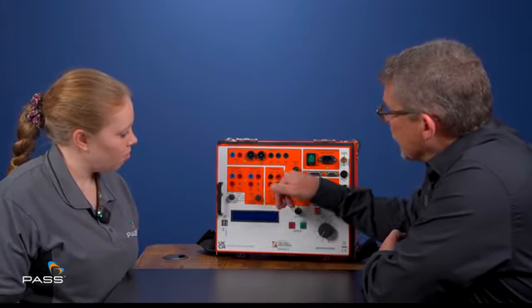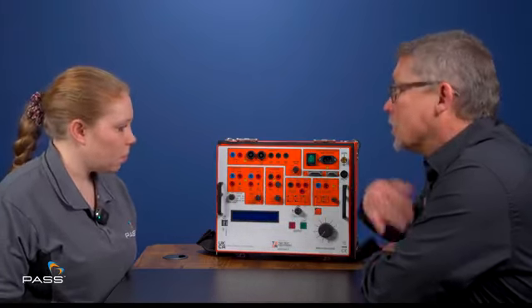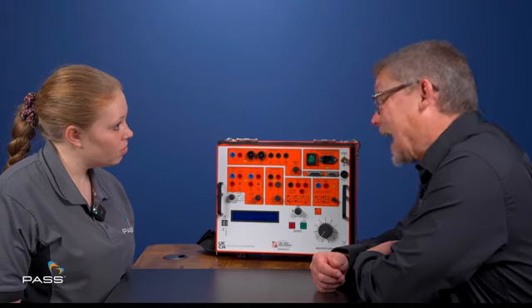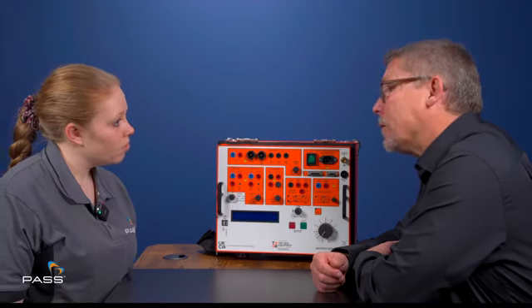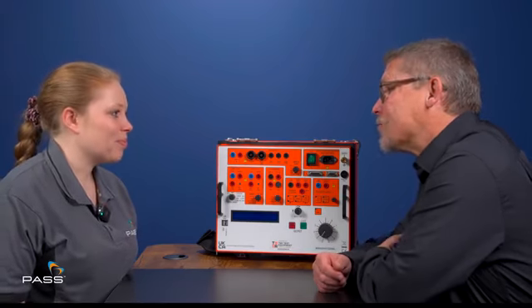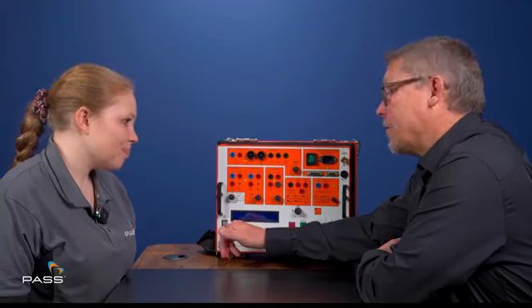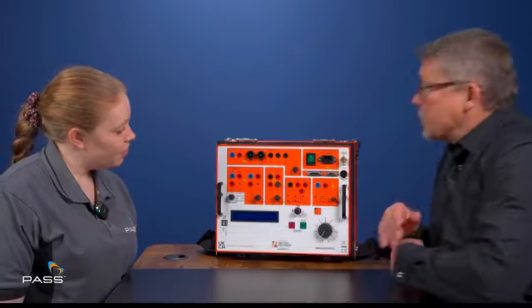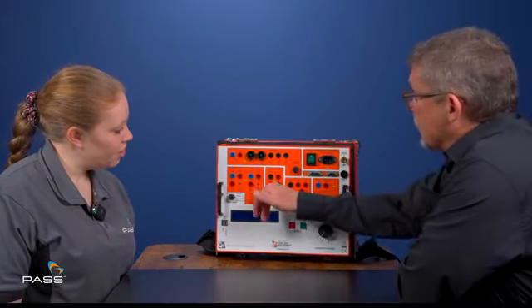And what we do is we use this as a reference for start and stopping the timer. To be fair, this is the one that I've least used myself. The others I use quite regularly, particularly the pulse, and the other one that I've used an awful lot when I worked for one of the boards, and that was for testing, as I said, the auto reclosers. You can do it with a manual tester, but you've got to be very quick at stopping the stopwatch and writing the results down. Obviously, the fact that we have that flash drive means that we can store that data nicely. And then the very last aspect we've got here is the auxiliary metering.